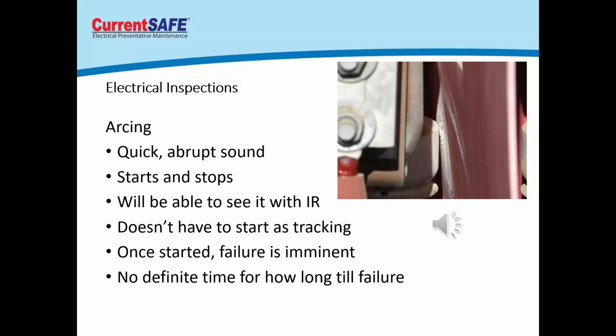You can see here, this is where the insulator was on the board. What had happened is the board, where it slides in between the phases, had come loose and leaned over onto the insulator, or at least that's where it ended up. It didn't start out that way, but it failed when it started to break down. That also causes vibration. So when we record this and play it back, you can also hear mechanical noise in that, meaning the vibration of that insulation board sitting there vibrating in that cabinet as well. So we can detect those kinds of things with that vibration. You can see there, this is where it was really close and leaning now because it had failed. The support system had failed with the insulator board.